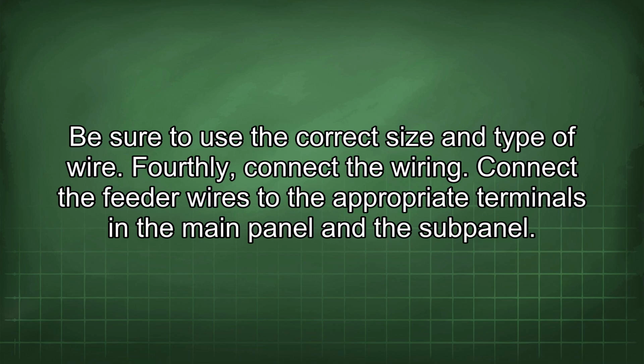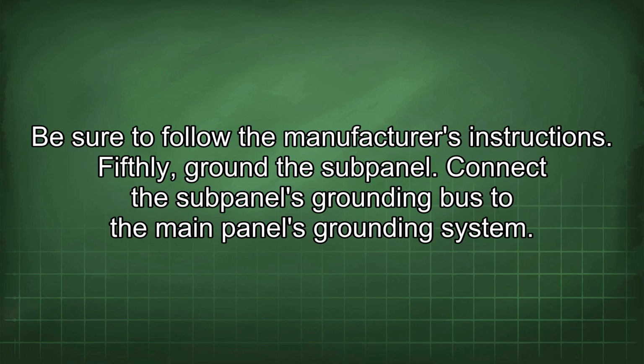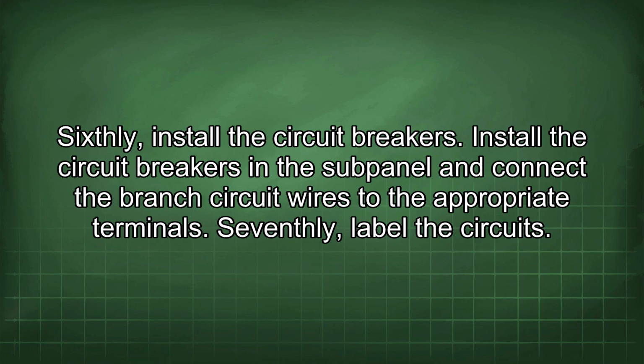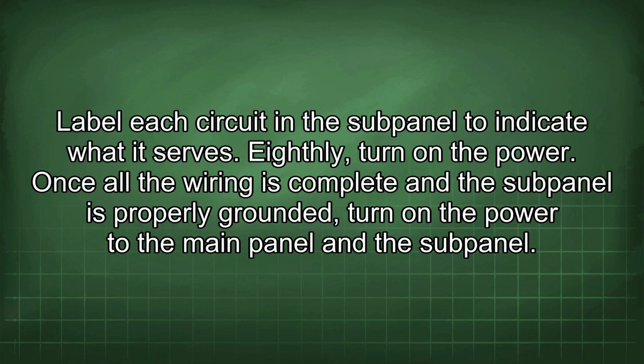Fourthly, connect the wiring. Connect the feeder wires to the appropriate terminals in the main panel and the subpanel. Be sure to follow the manufacturer's instructions. Fifthly, ground the subpanel. Connect the subpanel's grounding bus to the main panel's grounding system. Sixthly, install the circuit breakers. Install the circuit breakers in the subpanel and connect the branch circuit wires to the appropriate terminals. Seventhly, label the circuits. Label each circuit in the subpanel to indicate what it serves.